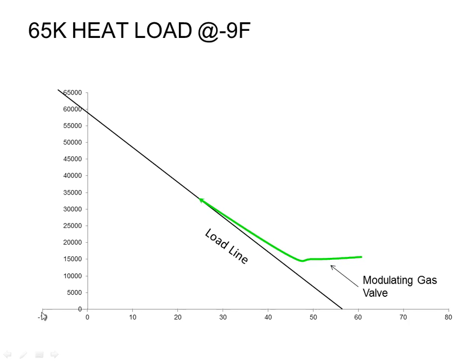This might show that pictorially. On the bottom scale here, we have -10 through 80 degrees of outdoor air temperature. On the left vertical scale, we have from 0 to 65,000 BTUs. So this particular house has a 65,000 BTU load on a minus 10 degree day, is basically what we're saying. And this black line represents this guy's load profile for his house. So it's easy enough to calculate for anybody's house if you wanted to. I can calculate the minus 10 degree load, and then I can calculate some of these other loads at 50, 55, 60 degrees and see when is it that this guy's house doesn't need any heat. So for this guy, when it's 57 degrees outside, he doesn't need any heat at his house.